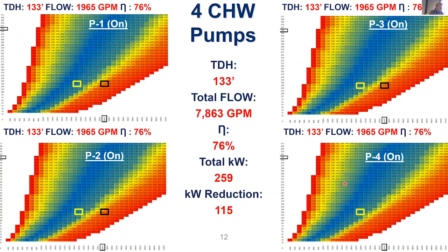Another important thing is to remember the first law of thermodynamics: that heat doesn't just disappear. That heat came out of the chilled water system. When I was wasting that 115 kW, we have an open drive motor, so 96% of that kW is going into the chilled water system. If I multiply that out, 3412 divided by 12,000, that is 31 tons of chilled water that I took off the chilled water plant. So I'm paying the utility to waste electricity, and then I'm putting that heat into the chilled water, and I'm paying the utility a second time to reject it out into the cooling tower.